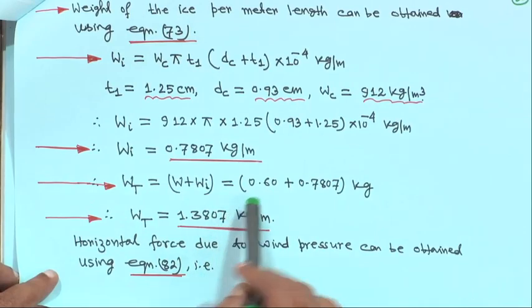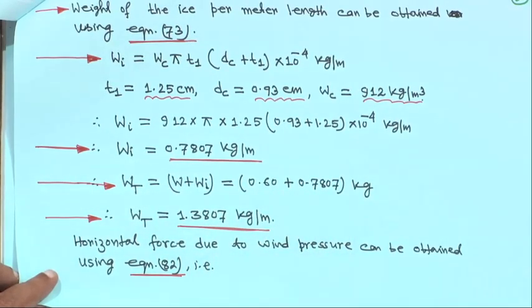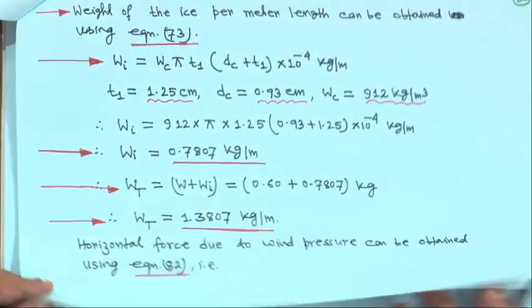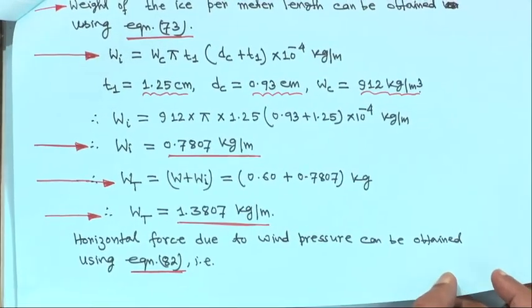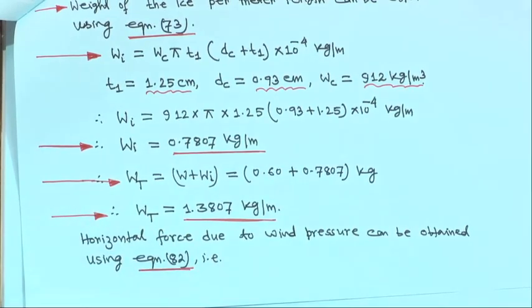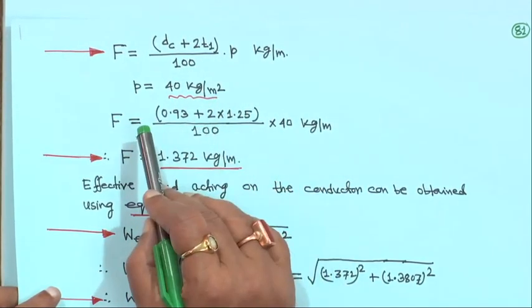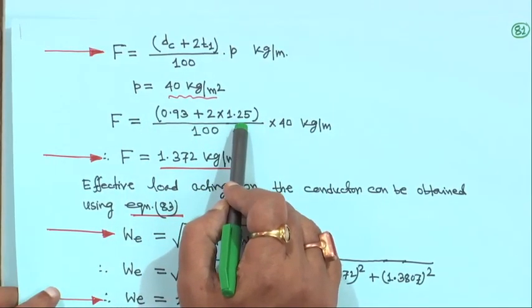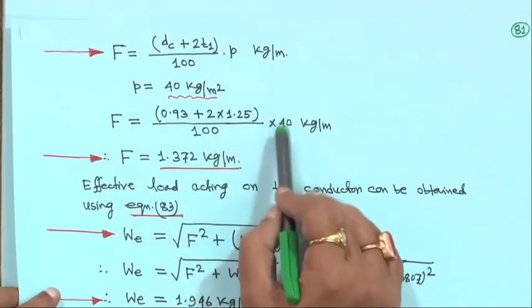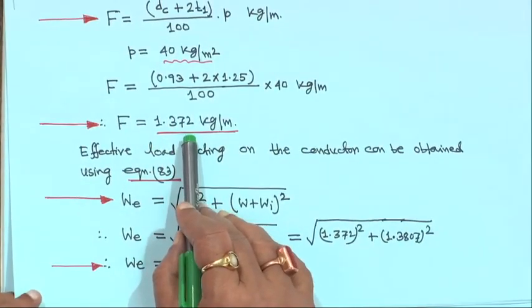Therefore Wt is equal to W plus Wi, that is 0.6 plus 0.7807 kg, giving total Wt equal to 1.3807 kg per meter. Horizontal force due to wind pressure using equation 82: F is equal to (DC plus 2·T1) upon 100 into P kg per meter. P is 40 kg per meter square, so F equals (0.93 plus 2 into 1.25) by 100 into 40, giving F equal to 1.372 kg per meter.